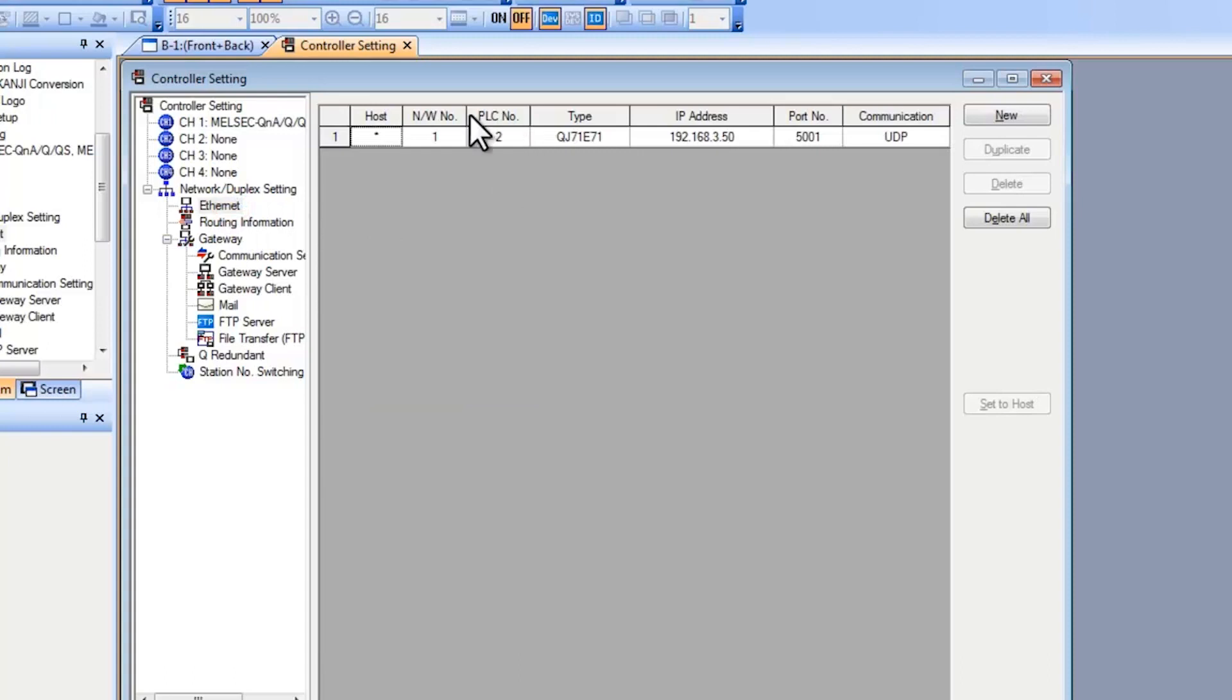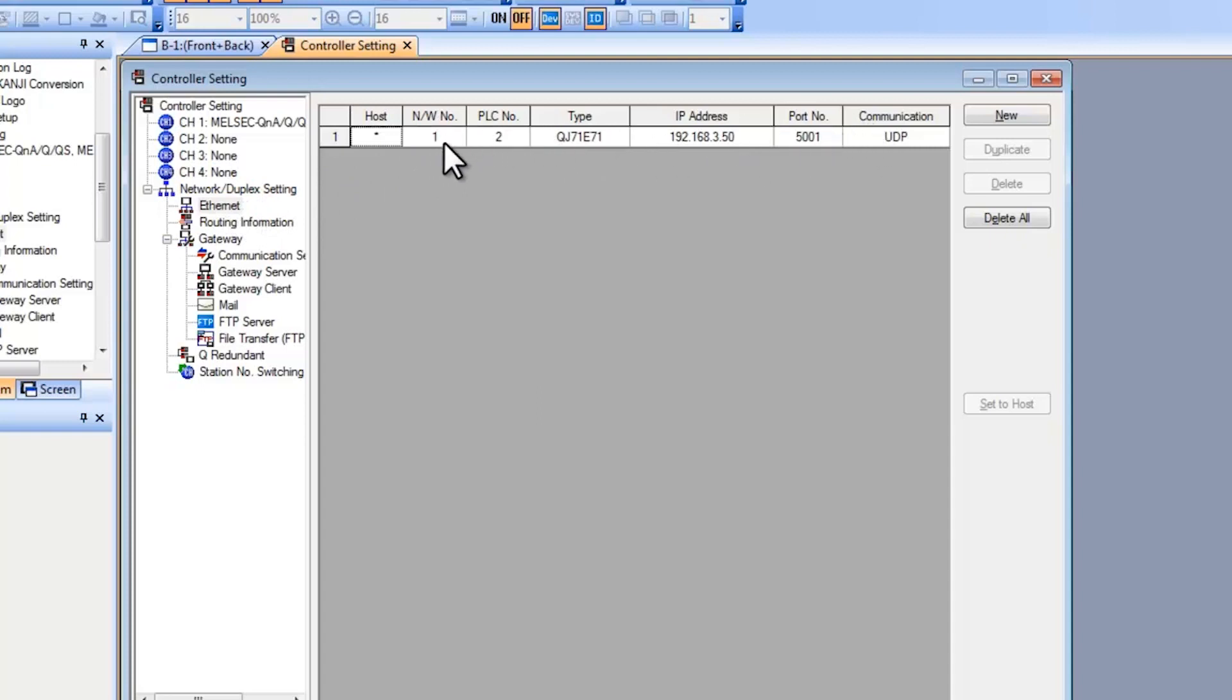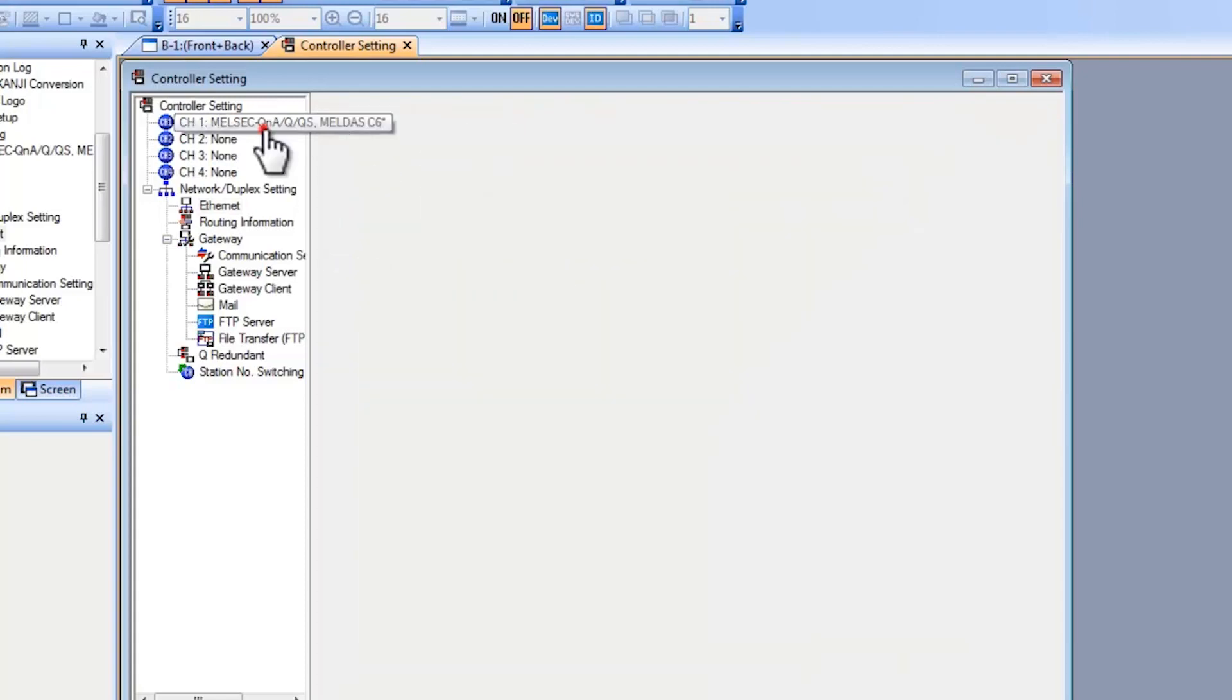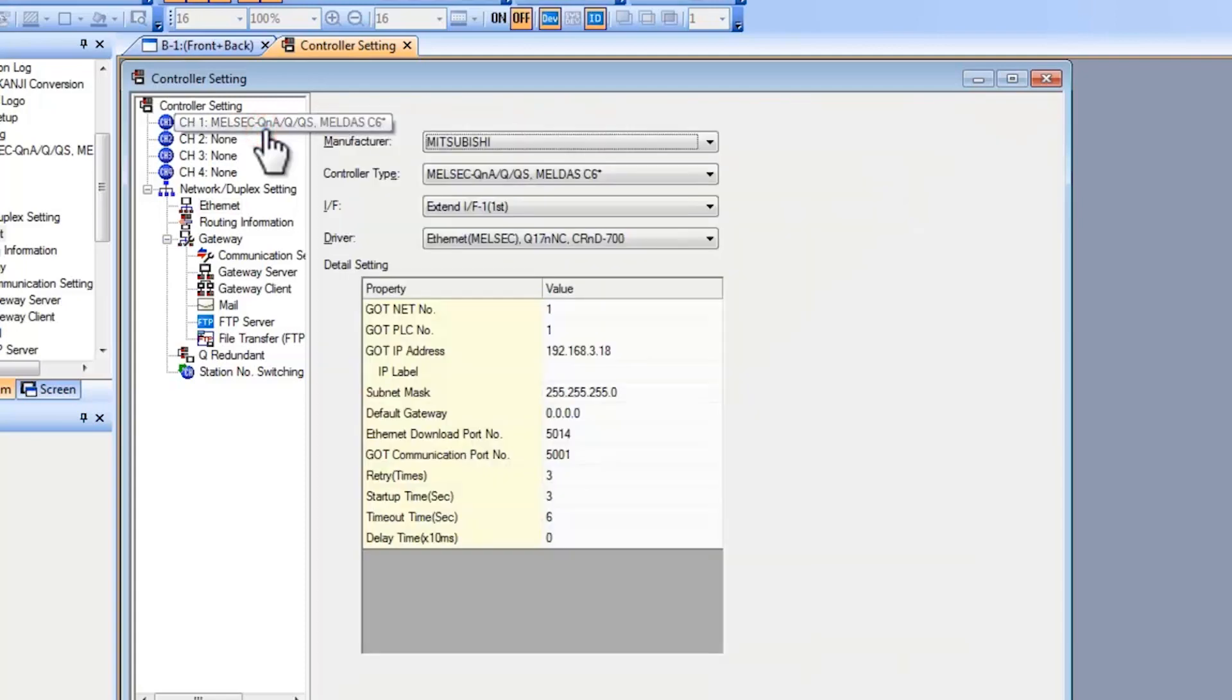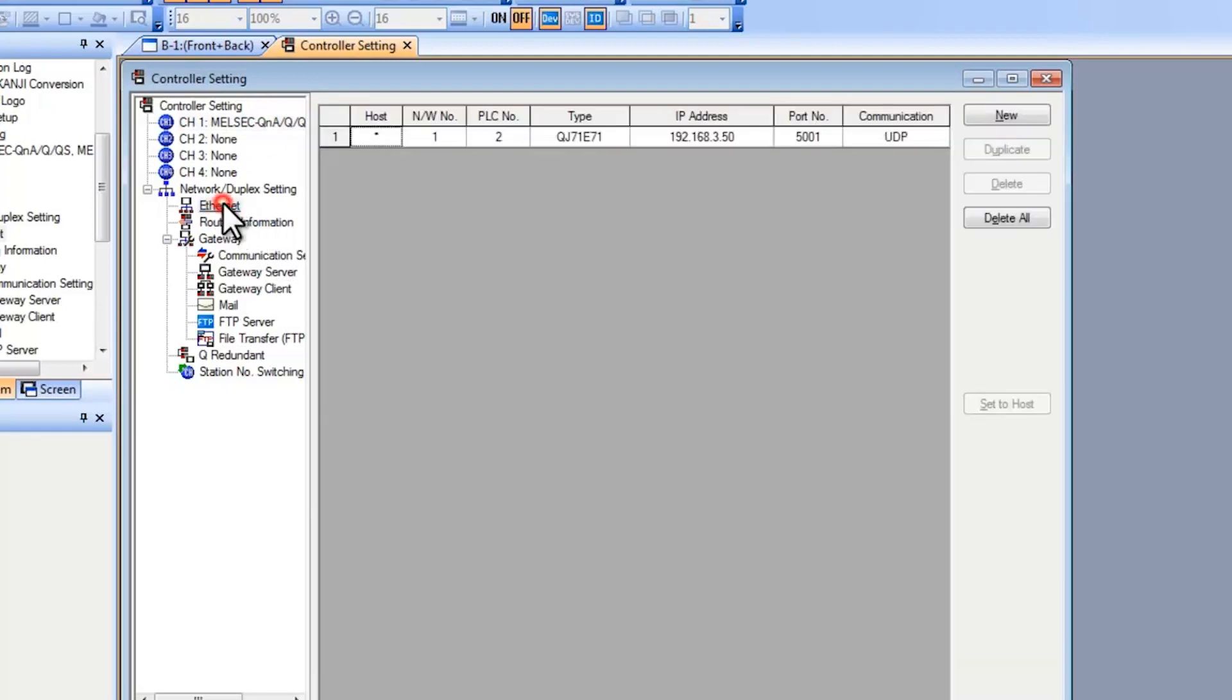Now for the PLC number this needs to match your PLC. In the Ethernet settings here on the GOT this is referring to your PLC. Your PLC number has to be different from the GOT PLC number. So if I go into channel here you can see my GOT PLC number is 1. For the controller it's 2.